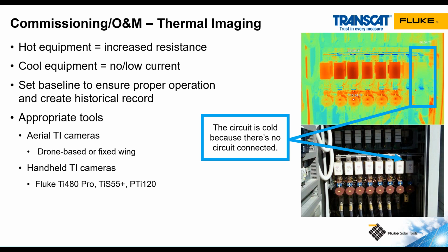Fluke has a whole line of thermal cameras. There are drone-based cameras out there. Fluke does not have a drone-based camera at this point. We have a line of handheld cameras starting from the small PTI 120, which is about the size of a cell phone. We have a new small entry-level thermal camera coming out called the IC, and that will attach to a smartphone and use an app to take the pictures. It actually has a higher resolution than the PTI 120 at a much lower cost, so that's going to be a good option.